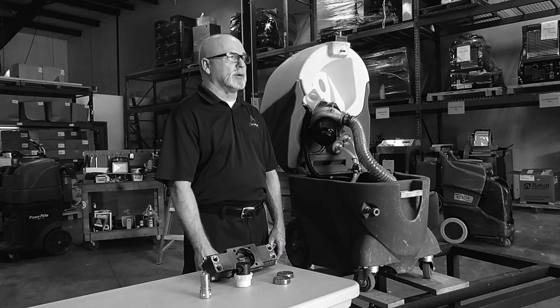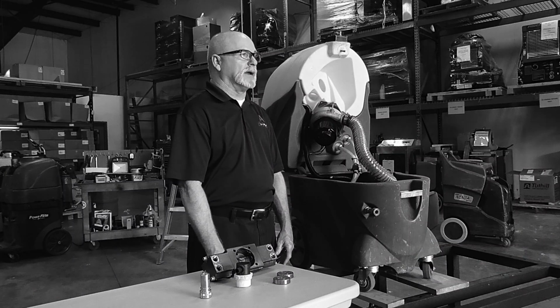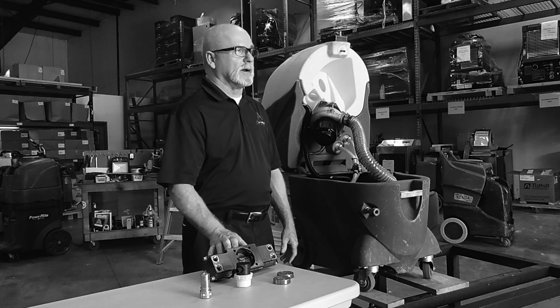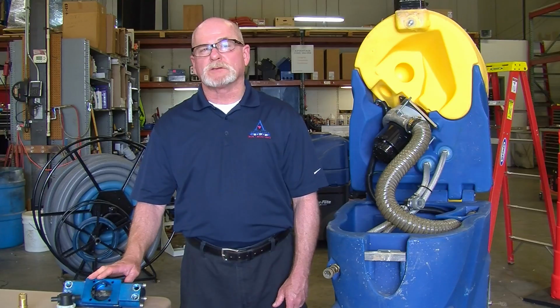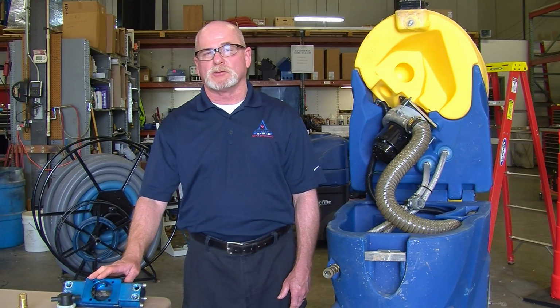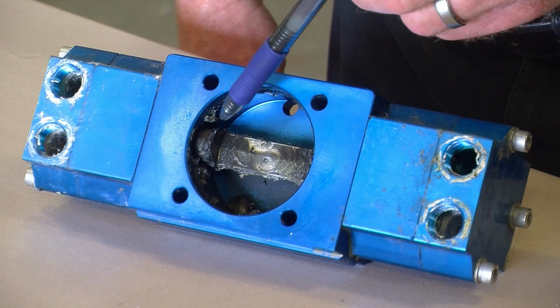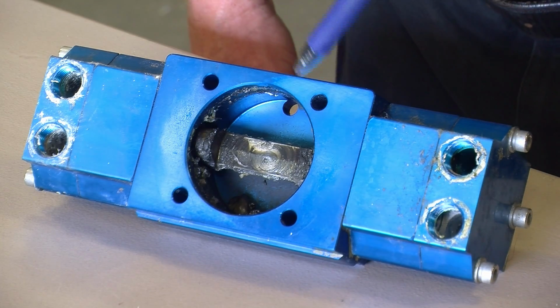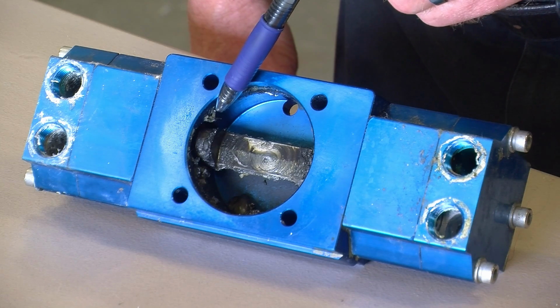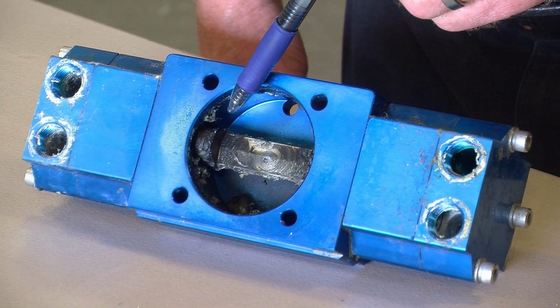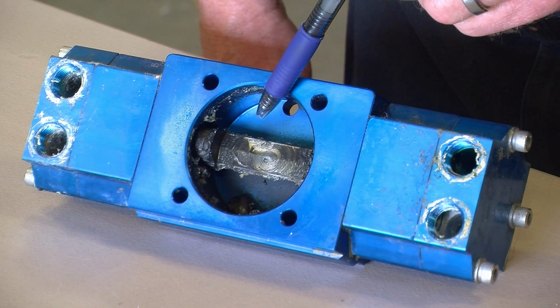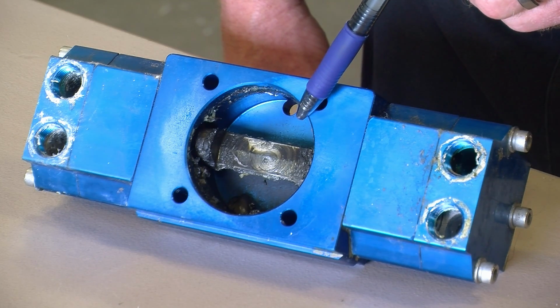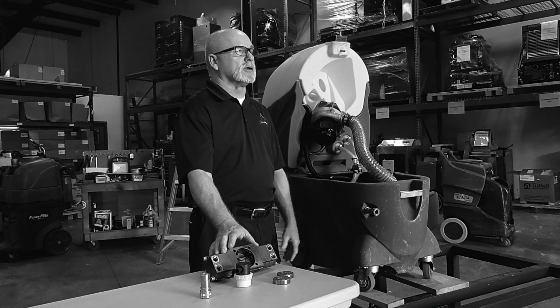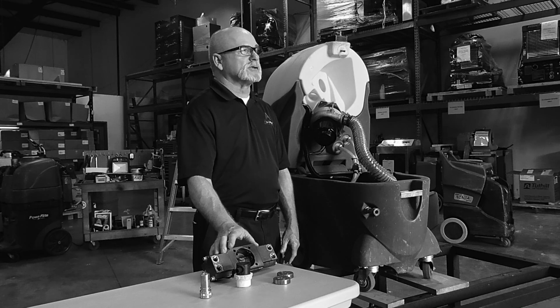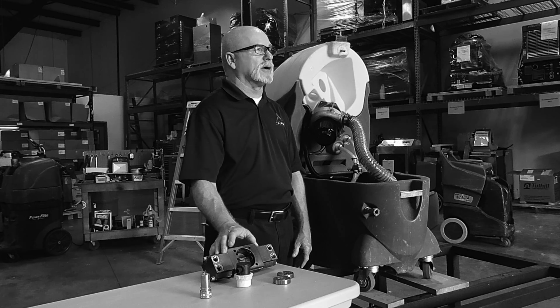I want to show you a pump head that has been ignored and not maintained. I have it here on my table, and once a year or every 500 hours you should disassemble this, clean it, and put a good white lithium grease on it and put it back in. You'll check your check valves, make sure there's no debris. Those are pretty durable. But what happened is this unit came in due to an excessive noise. The customer got used to the loss of water pressure, but it was the noise that had increased, because the noise is the final warning sign that the head has expired.